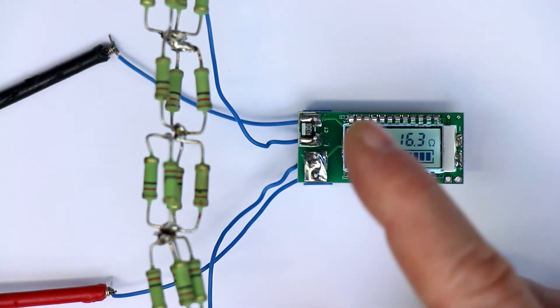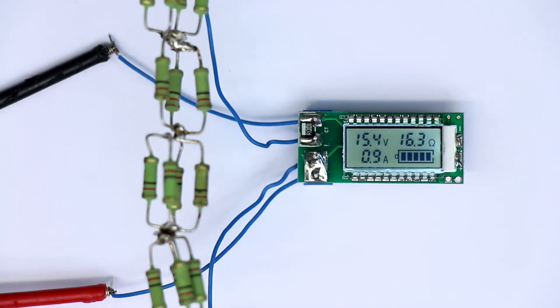Here and also this is exactly to what this resistor combination here above is: 16 ohms plus minus 10%, and the accuracy stated is 2% and this seems reasonable. You even can recalibrate it by inputting 10 volts and 1 amp.